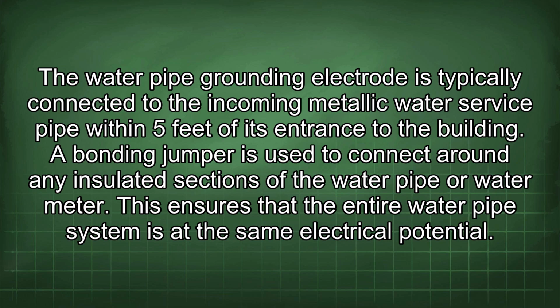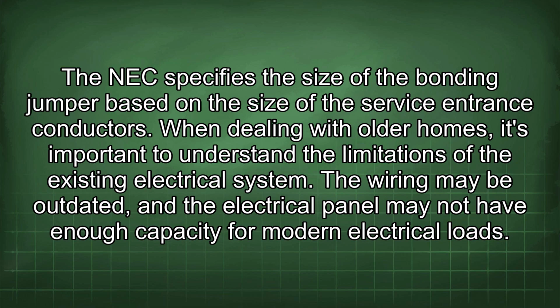The water pipe grounding electrode is typically connected to the incoming metallic water service pipe within 5 feet of its entrance to the building. A bonding jumper is used to connect around any insulated sections of the water pipe or water meter. This ensures that the entire water pipe system is at the same electrical potential. The NEC specifies the size of the bonding jumper based on the size of the service entrance conductors. When dealing with older homes, it's important to understand the limitations of the existing electrical system. The wiring may be outdated, and the electrical panel may not have enough capacity for modern electrical loads.